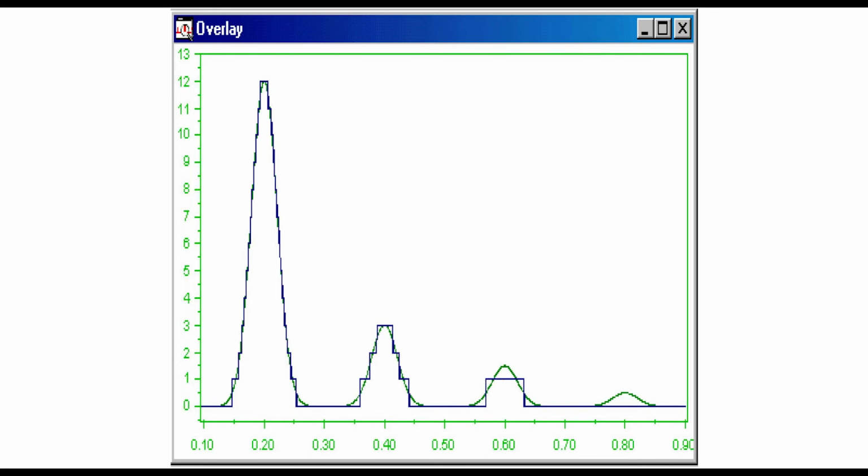Accuracy will suffer when the errors introduced by the rounding off process are on the order of the peak height. The usual rule of thumb states that, for accurate measurement of peak height and area, the peaks should be at least 10 steps high. Peaks smaller than this may still be detected, and sometimes this is enough.